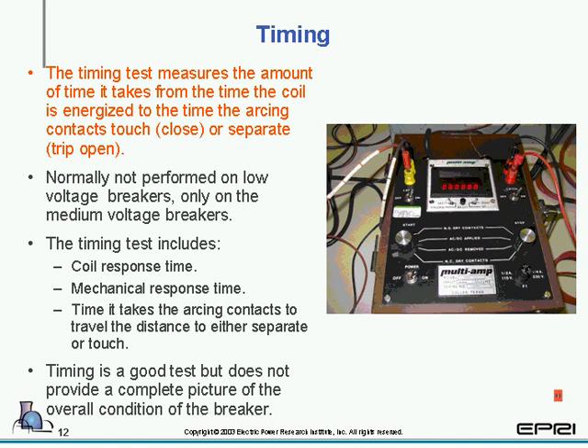For those of you taking the test, you might want to remember the very first paragraph. The timing test measures the amount of time it takes from the time the coil is energized to the time the arcing contact touches or separates. One of the main ideas is what it does not tell you: the overall condition of the equipment. Quite often I hear people say, well, our timing's good, so the breaker's got to be operating correctly. That's not truly true.